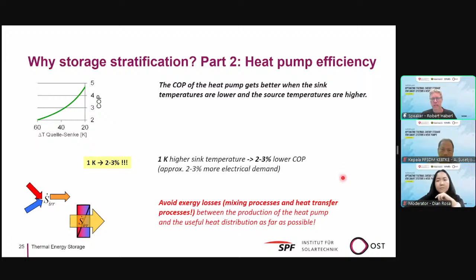The second reason is the efficiency. I talked about solar thermal collectors that are more efficient if the temperature is low, but the same applies for the COP of a heat pump. It gets better when the sink temperatures are lower and the source temperatures are higher. 1 Kelvin higher sink temperature means a 2 or 3% lower COP of the heat pump. That means with every Kelvin the lower part of the temperature of the storage tank rises, the efficiency drops, and therefore you have to avoid exergy losses and mixing processes and heat transfer processes inside the storage tanks.